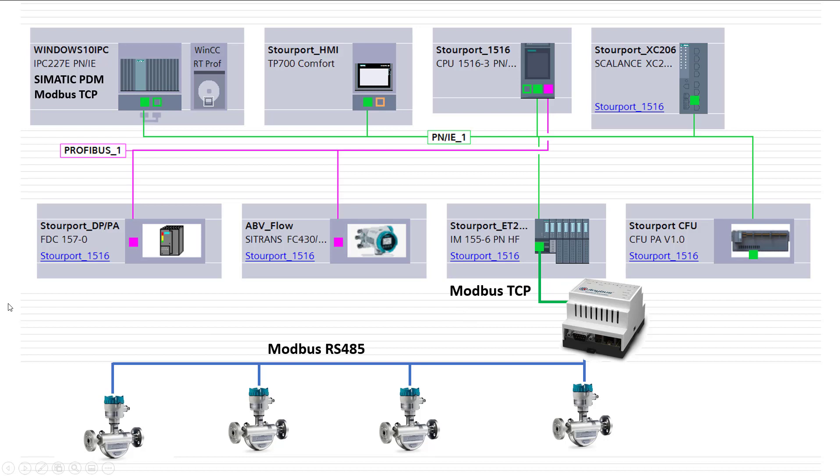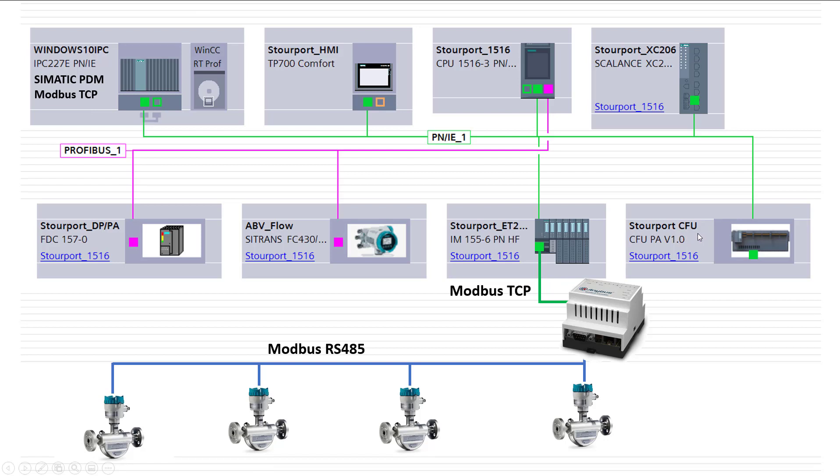And that will give me not just Modbus connectivity all the way down from my central engineering station for my Coriolis meters, but if I have—if you look at this example—I've got a Coriolis meter on PROFIBUS PA on a transparent coupler, so those two devices will come up to PDM. Any HART IO I have on here, so any HART instruments on the ET200 SP, can also go to that. If I'm using the ET200 ISP for hazardous area, then again I can bring that up to here.